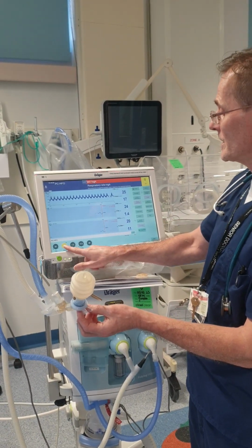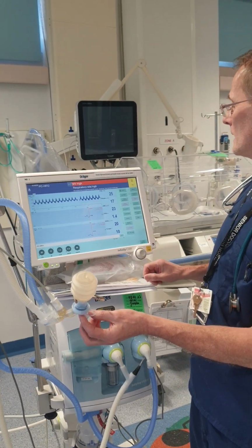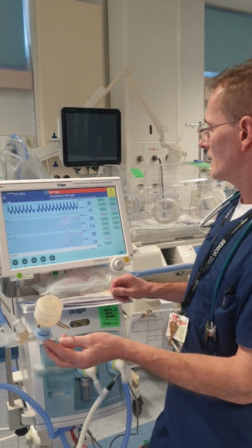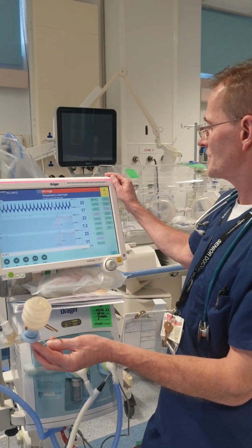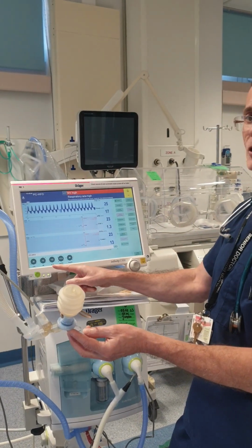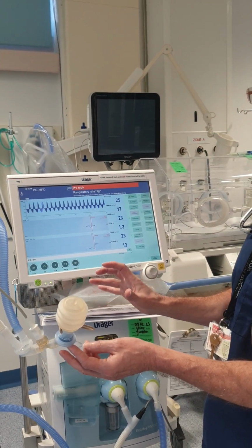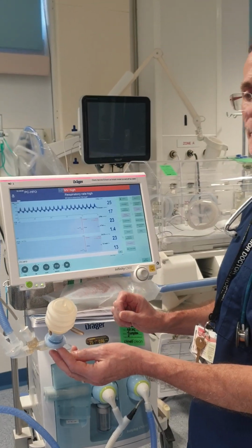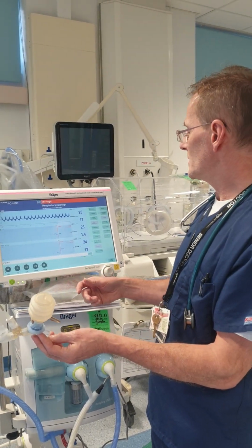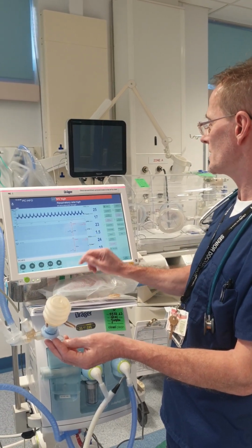For the purposes of demonstration, I'll turn this down one more. And let's see what happens here. Give it a wee second. The delta CO2 has come up to 23. Manipulating the frequency in oscillation is a very powerful means of clearing CO2, but we largely want the consultants to be directing that sort of thing, or if you're not comfortable with the machine. So having dropped the frequency to 13, I've got a tidal volume in oscillation of 1.5.